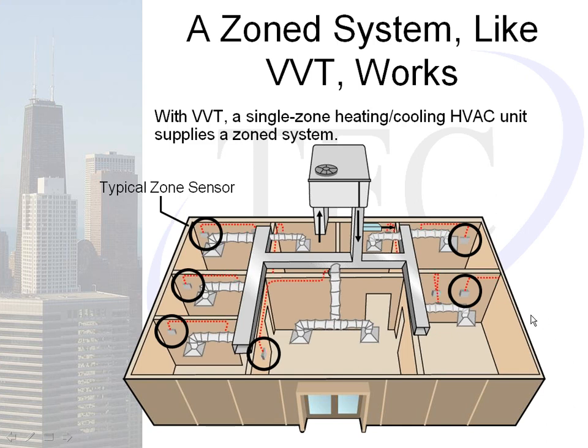When the sun is rising on the east, the southeast and northeast corners will call for cooling. On the west side of the building, there may be no need for cooling because it's cooler or unoccupied. Those dampers will close, the east-side dampers will open, and the rooftop will go into cooling mode, providing air where it's required.